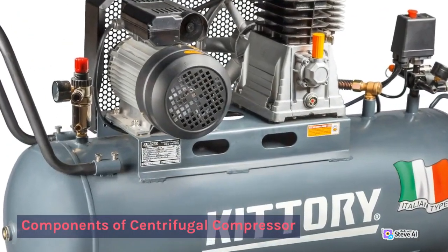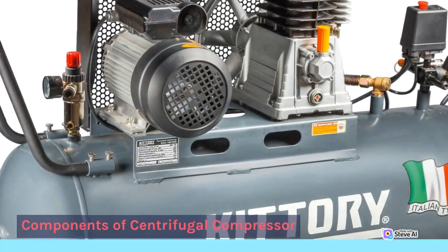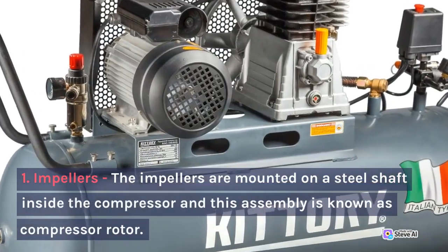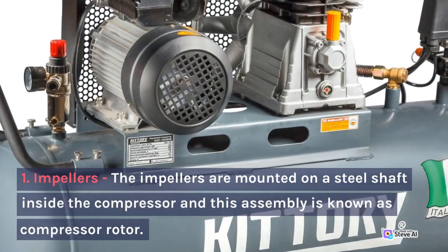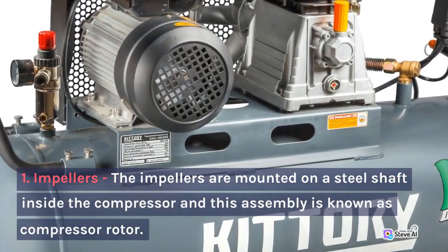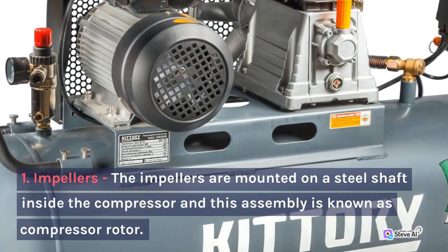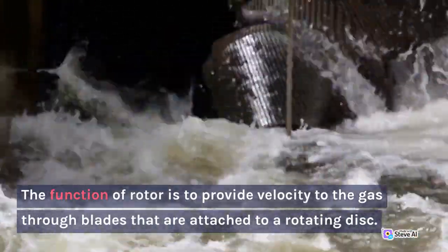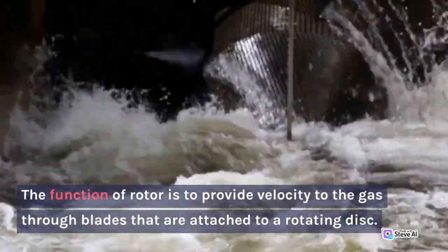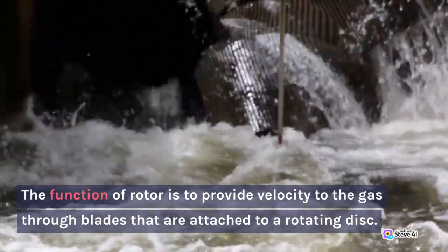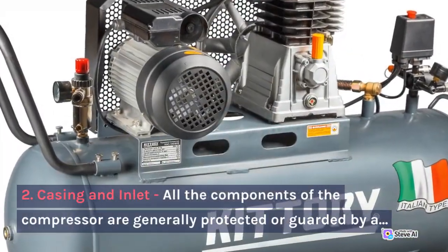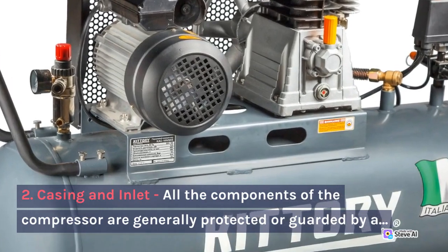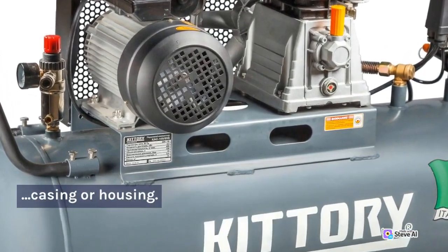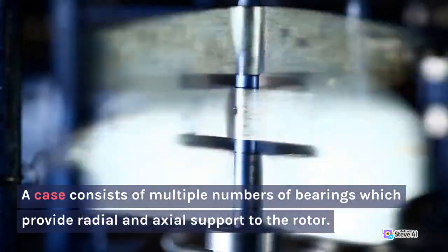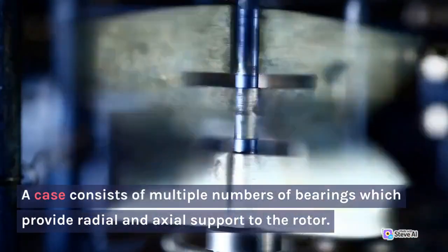Components of centrifugal compressor. 1. Impellers. The impellers are mounted on a steel shaft inside the compressor, and this assembly is known as the compressor rotor. The function of the rotor is to provide velocity to the gas through blades that are attached to a rotating disc. 2. Casing and inlet. All the components of the compressor are generally protected or guarded by a casing or housing. A case consists of multiple bearings which provide radial and axial support to the rotor.